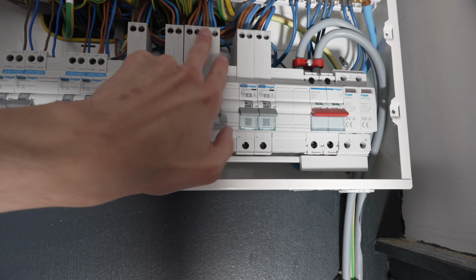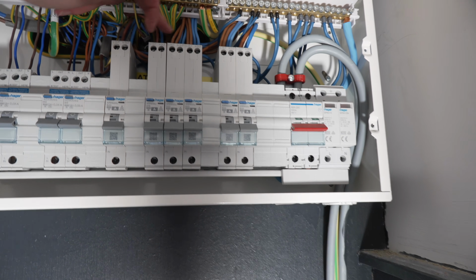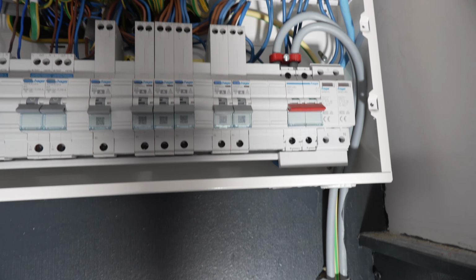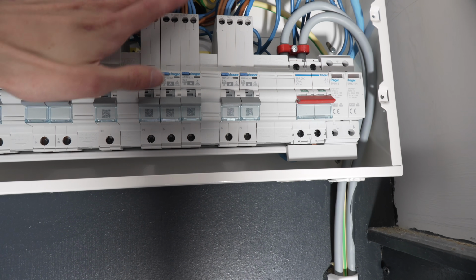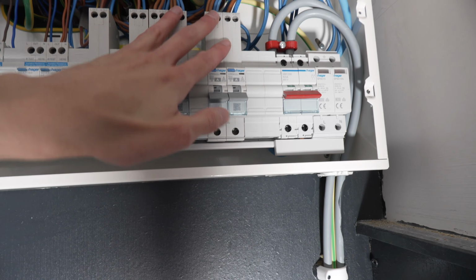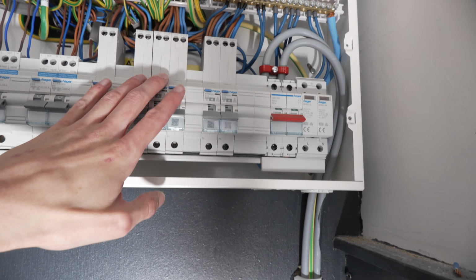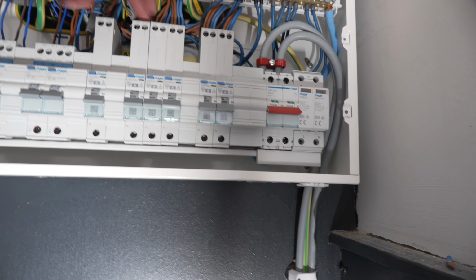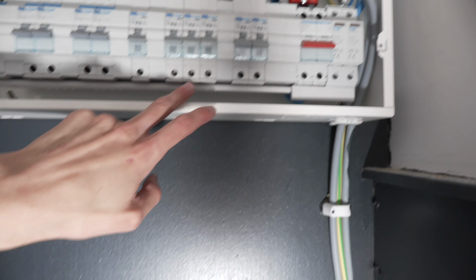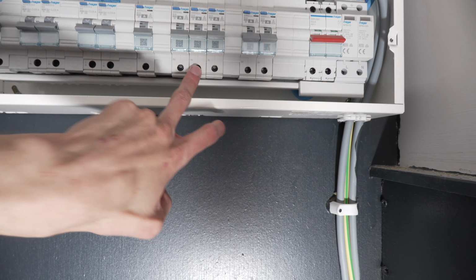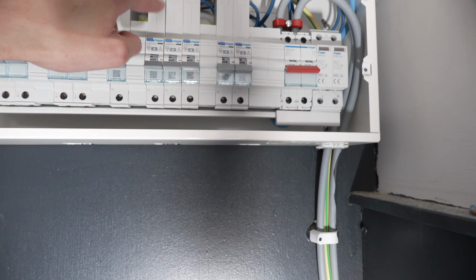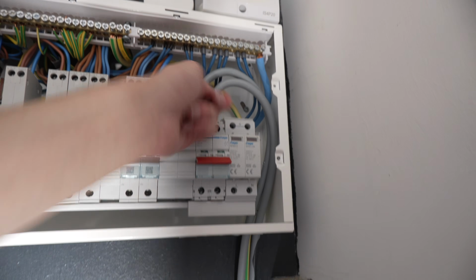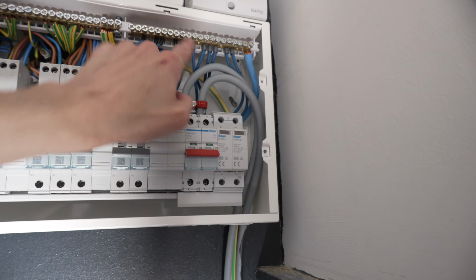But then the sockets ones and the kitchen ones, there is no chance I'm going to get a CT around these without really bending them and contorting things. So instead for these two circuits, what I'm going to do is use the neutral fly leads, because these being essentially RCBOs, they have line and neutral in at the top, and live in at the bottom from the bus bar, but then the neutral is carried in over these fly leads that connect to this neutral bar over here.